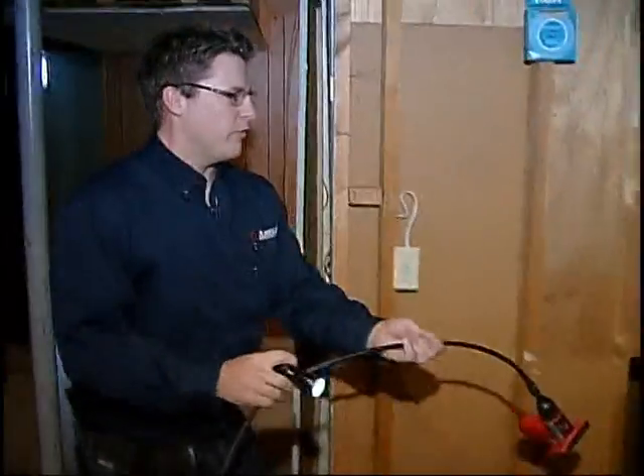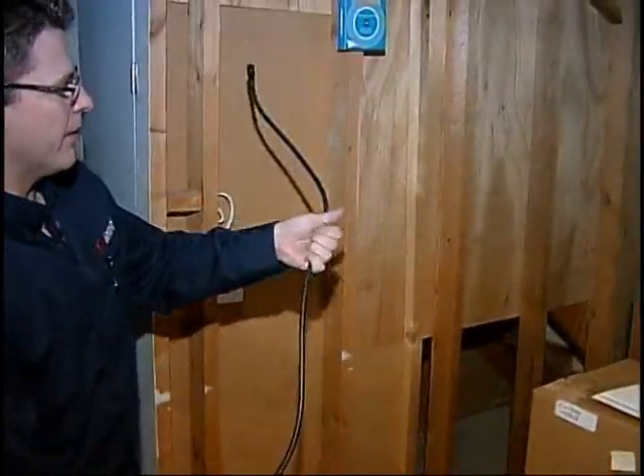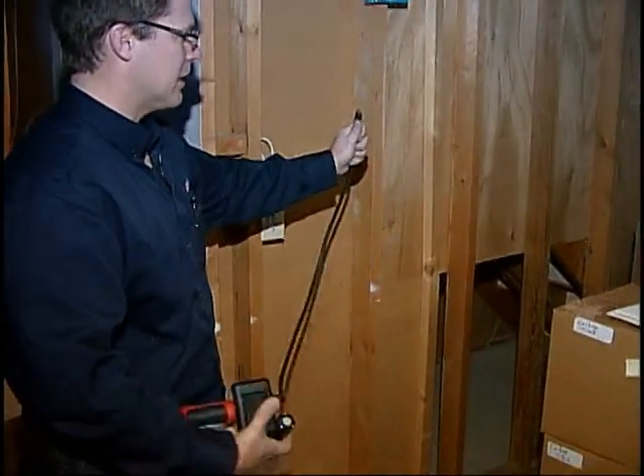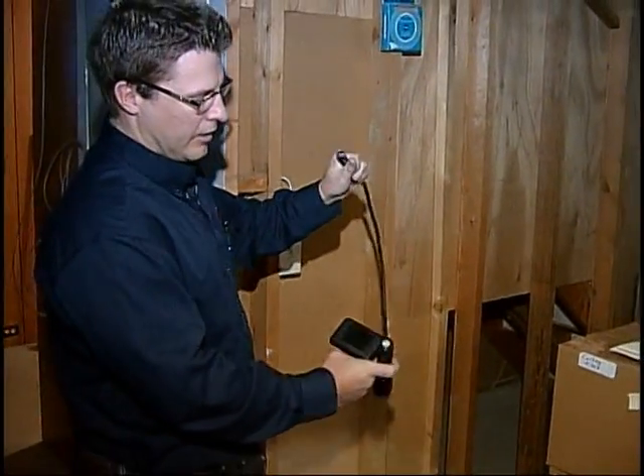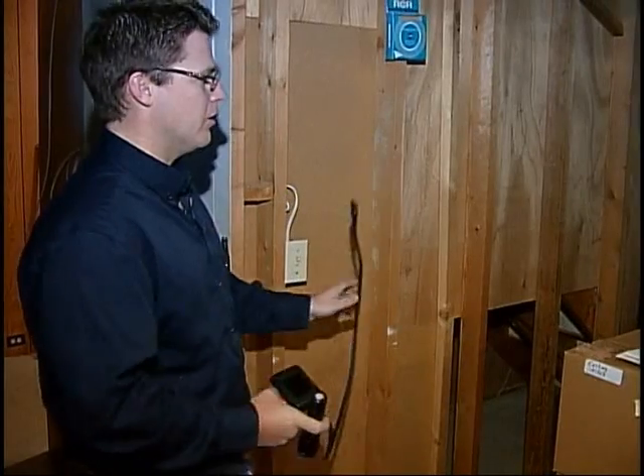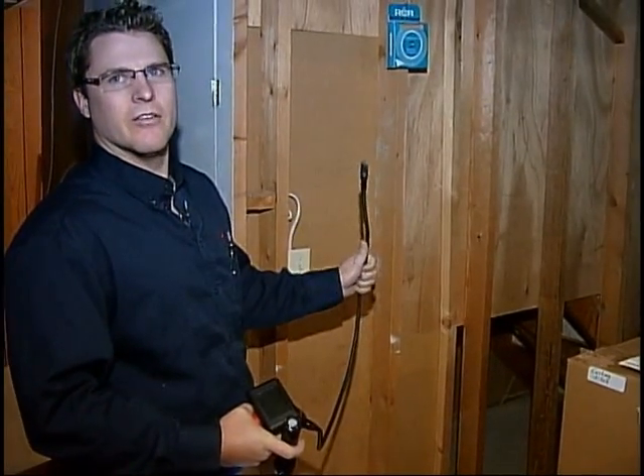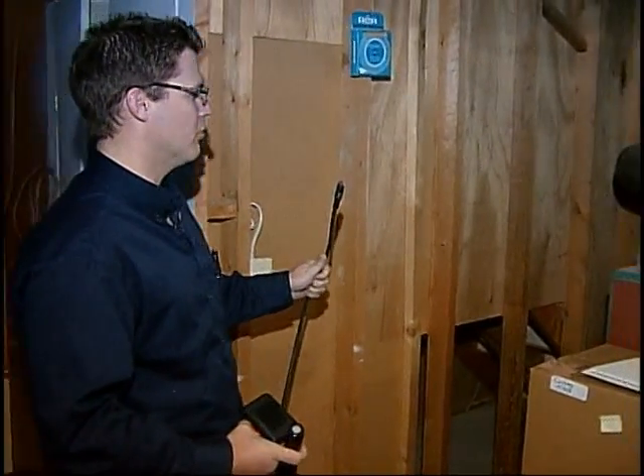The most important gas we're testing for is actual carbon monoxide. So what I'm going to do now is use what we call a borescope, which has a little camera on it and a little sight lens here where I'll be able to actually look right up into the heat exchanger and inspect it for any cracks or holes.